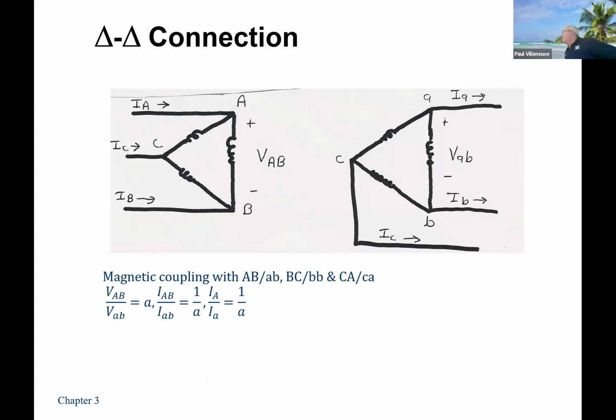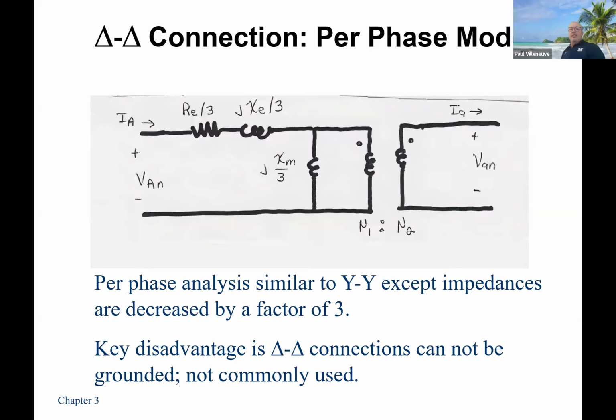Here's a delta-delta, very, very uncommon. I don't think I've ever actually, oh no, I've seen one delta-delta. If you look at the Millinocket Dolby one, they actually have a delta-delta transformer. So again, the voltages are the same, so the turns ratio is exactly the same, and there's no phase shift between primary and secondary. So over here, in my equivalent, you would divide by 3 because this is a Y equivalent representation of a delta. If you want to keep it in a delta, that's fine. Just recognize that those will be multiplied by 3. So that's where the divide by 3 comes from, because you're representing it as a Y equivalent.